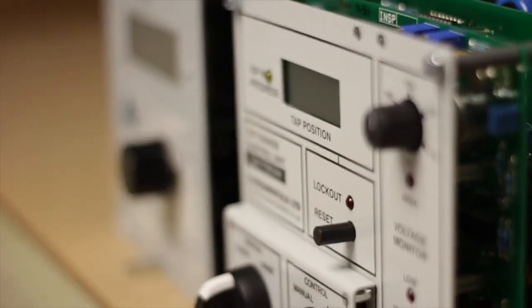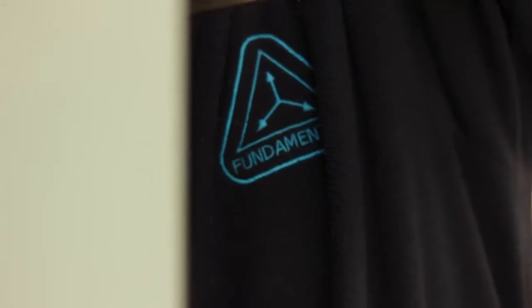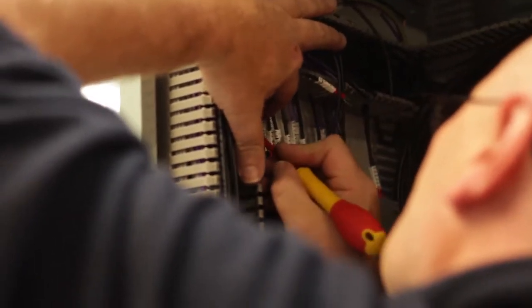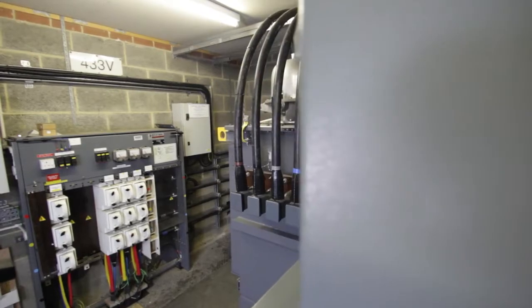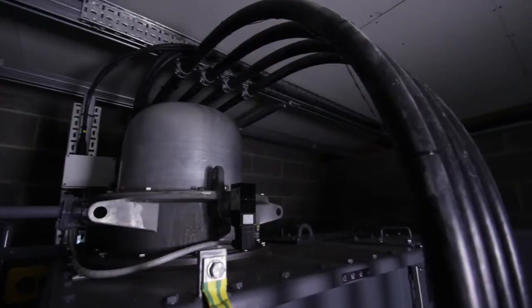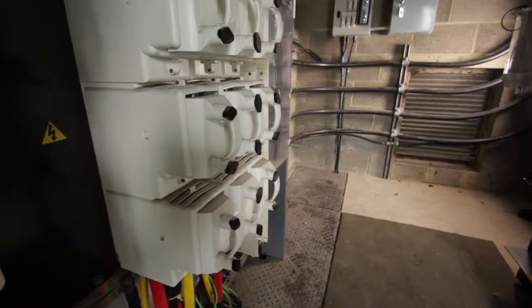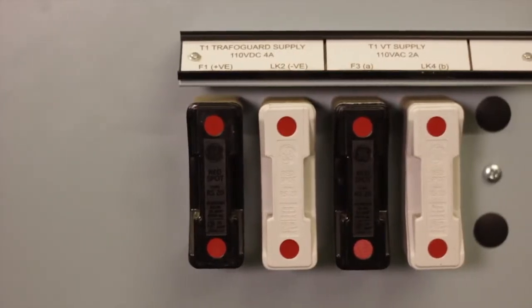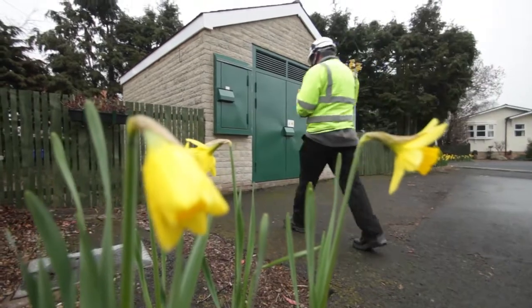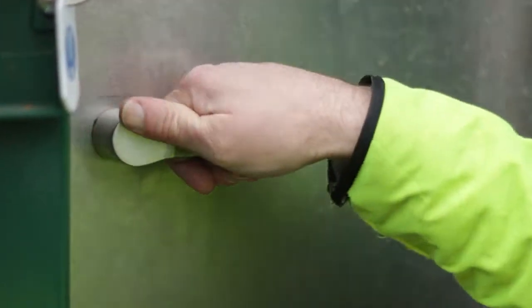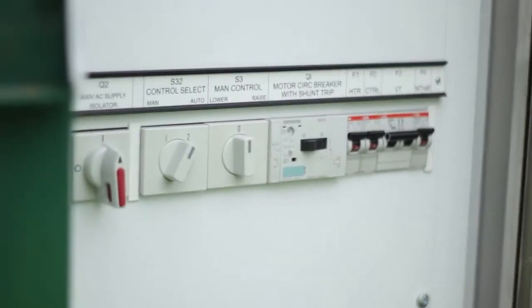There are different solutions required in terms of voltage control, and we've designed and manufactured the relays and equipment which can cope with the new requirements and challenges for distribution networks. Traditionally, the tens of thousands of distribution transformers which the DNOs own have off-load tap changers, so they have 5 or 6 switching positions to modify output voltages. If you need to change a tap position on a traditional distribution transformer, it requires an outage - not great for consumers. So the on-load tap changer allows voltage regulation without those interruptions.